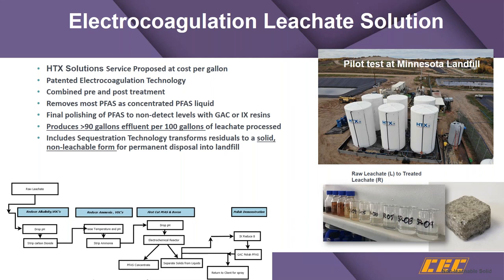Electrocoagulation is a process that can help remove and destroy PFAS constituents. It requires a lot of pretreatment because without it there's going to be a lot of foaming — alkalinity has to be removed either biologically or stripped out. The residual is a smaller amount. One company we've been speaking with is HTX down in Texas; they have a patented technology and approach this as a service, charging a cents-per-gallon fee with very little initial capital expenditure.